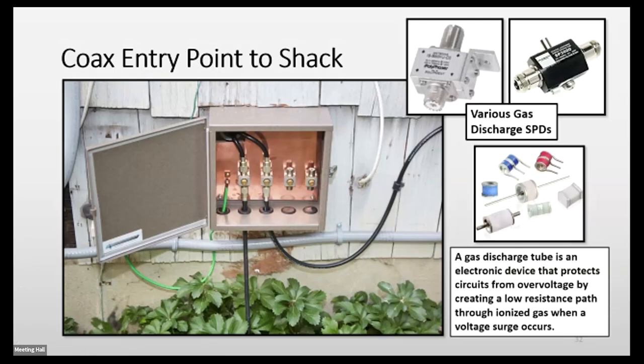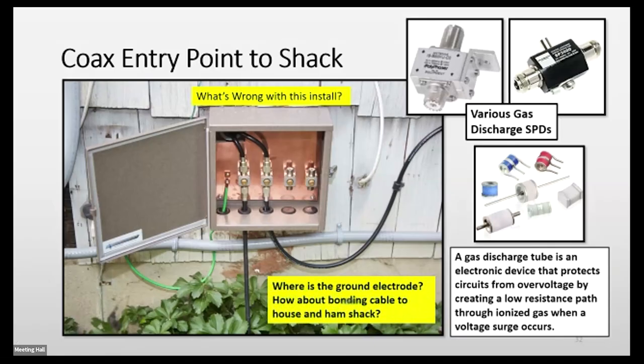But one more thing here - what's wrong as you see this? What do you see that's wrong here? You got to look closely. Yeah, that's right, there's no ground electrode. Maybe it goes somewhere, I have no idea where it goes. It might go to the ground - there on the far left side there's a ground cable. It might be for the cable company, it might go over and clamp to it. It certainly is not what I would consider acceptable for my use if I were putting it in. I mean, it's a great idea to have it, but somebody didn't go far enough.